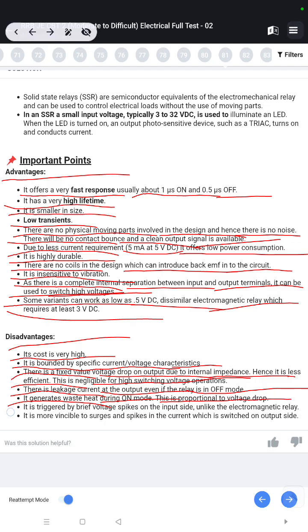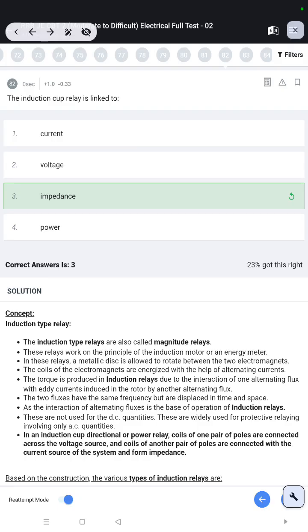It is triggered by brief voltage spikes on the input side. Unlike the electromagnetic relay, it is more vulnerable to surges and spikes in the current which is switched on the output side. The induction cup relay is linked to impedance. Induction type relay.